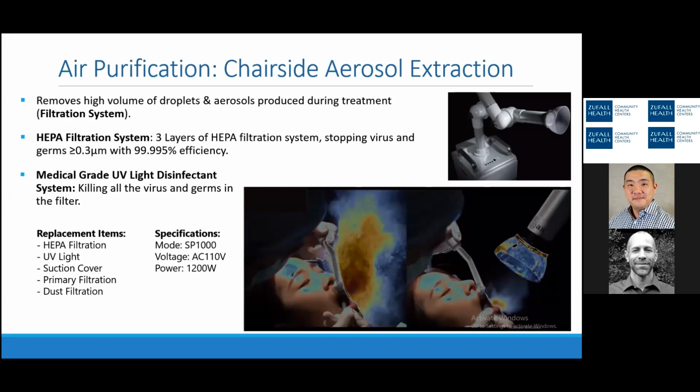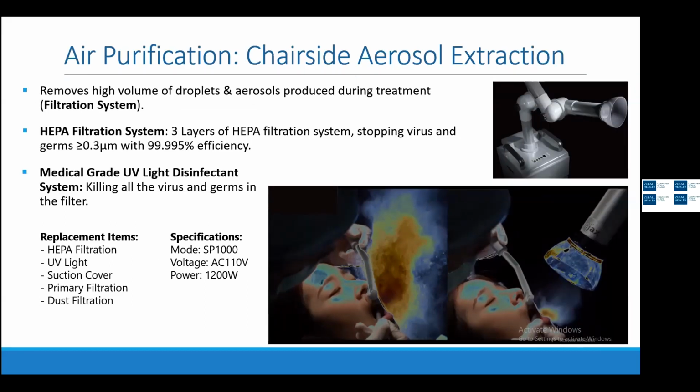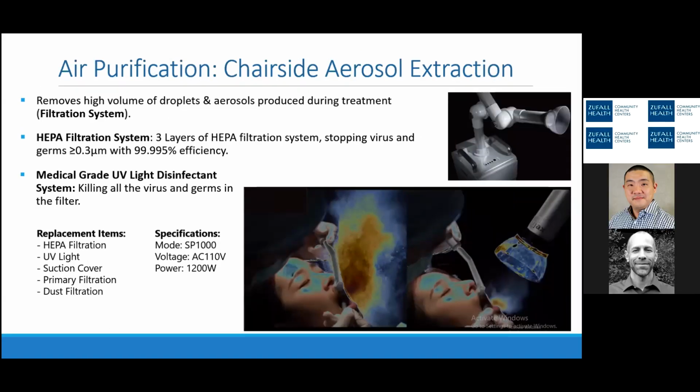And so we can see based on the specs, some of the information I was able to find, that these devices are good at removing particles greater than 0.3 microns. They do contain a UV light for a disinfectant system, but it's important to note that these lights will only disinfect or inactivate pathogens that are actually trapped on the filter itself. So for viruses that pass through the filter, the residence time is so short the UV light is not effective at inactivating them.